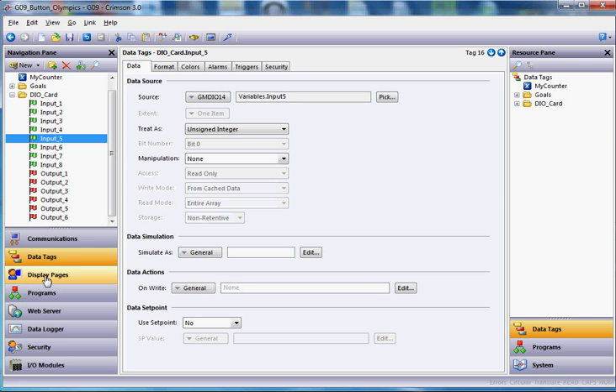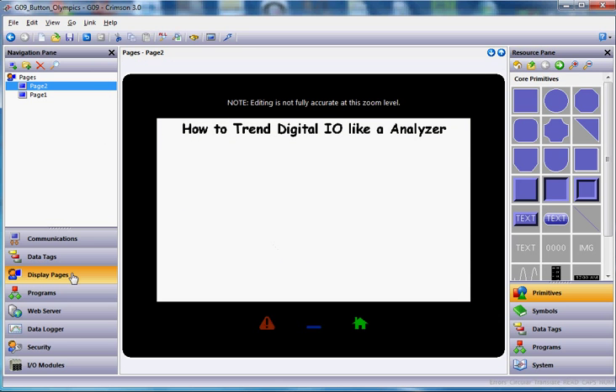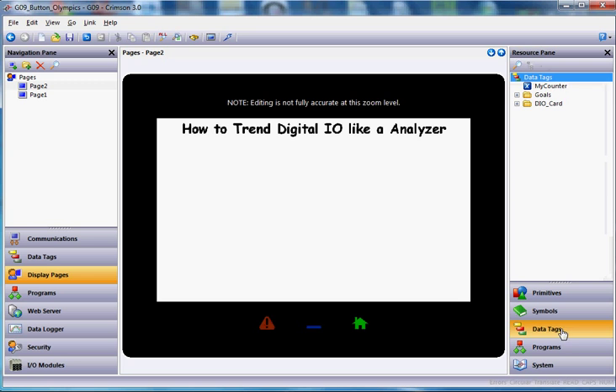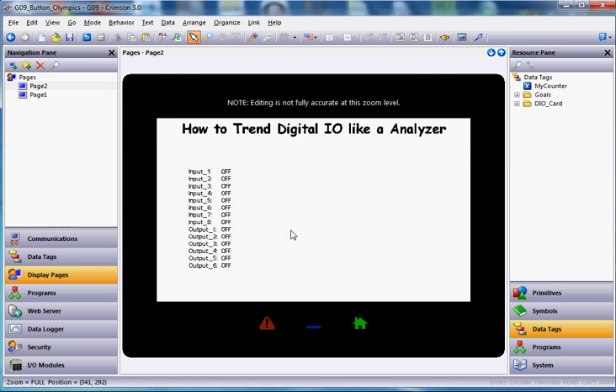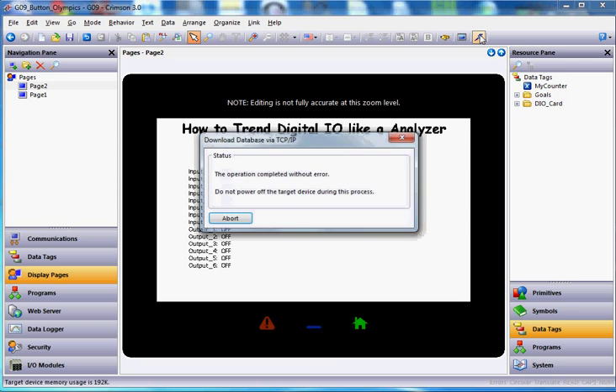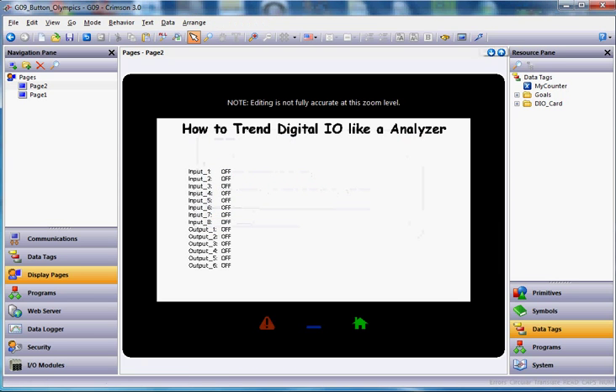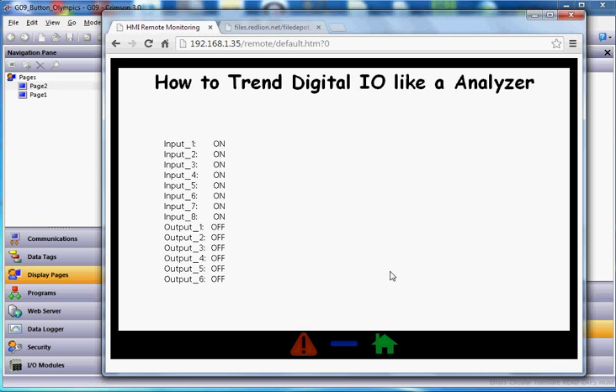So just to show first of all that on the screen, make sure it's working. I'll go over here to the left-hand side and click display pages on the left. And I'll go over here to the right and click data tags on the right. And I'm just going to grab this folder of tags and put it on the screen here. And let's go ahead and download this to our HMI here. And once I download, if I open up the browser, you'll see here, once the card starts registering, you'll see that I can turn on and off my discrete inputs. Now these are all sinking inputs, so I tie them to the negative side, and that will give me an off signal. So by default, they're all on until I take them to zero, then they go to the off state. So I currently have a couple push buttons connected to input one and two.